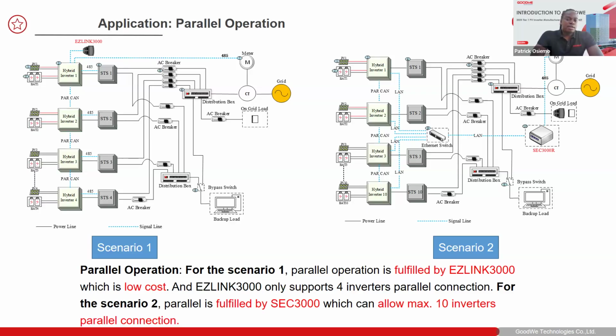As you can see, we can share the loads on both the grid side and the critical side, so we can parallel. Then in case you're doing more than 4 pieces of the 50 kilowatt, then it is possible. You can do a maximum of up to 10 pieces, and you'll be needing the GoodWe control box called the SEC 3000C. And you'll be achieving up to 500 kilowatt of AC. And on the battery side, you can do up to 4 megawatt hour, depending on which battery you're choosing.